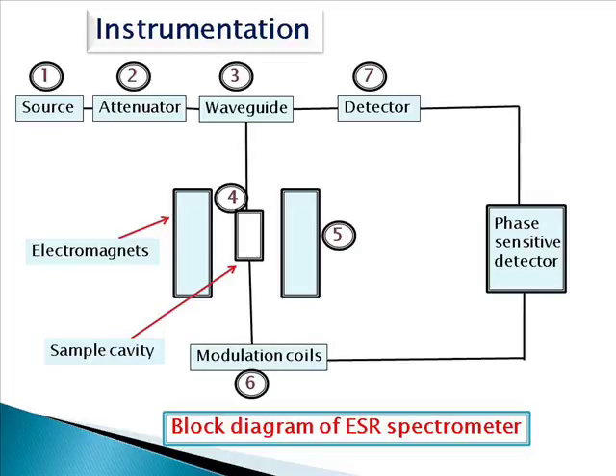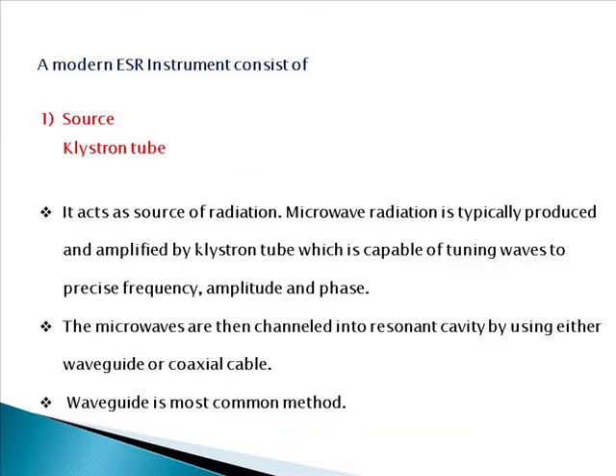The first component of a modern ESR instrument is the source, which is a klystron tube that acts as a source of radiation. Microwave radiation is typically produced and amplified by the klystron tube, which is capable of tuning waves to a precise frequency, amplitude, and phase. The microwaves are then channeled into the resonance cavity using either a waveguide or coaxial cable — the waveguide being the most common method.